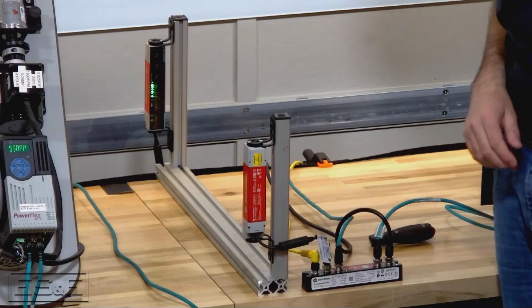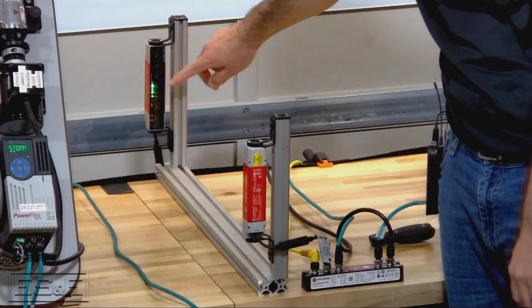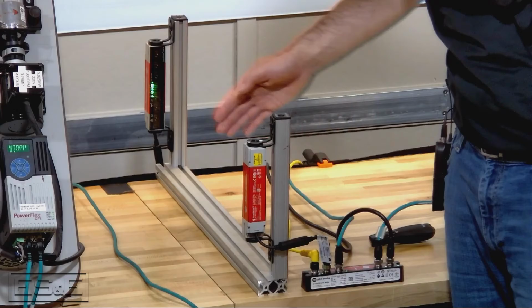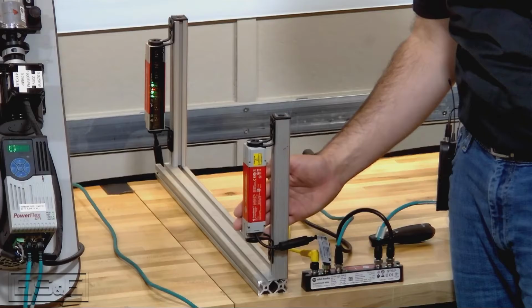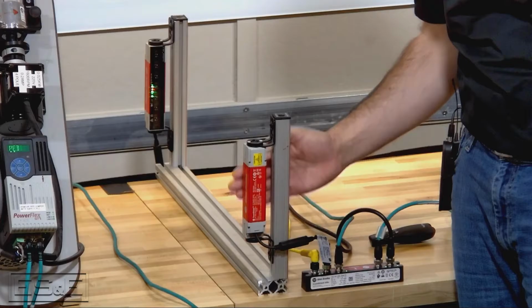The light curtains themselves have diagnostics, just a light level of visual diagnostics. It tells you whether or not you've broken the beam. It tells you if you're on a particular segment. So there's two segments on this, so it lights up depending on which segment I have broken. And then if I cover the whole thing, I lose all segments, right?